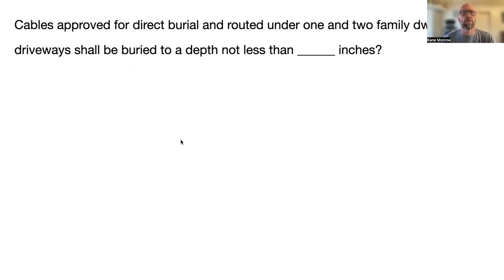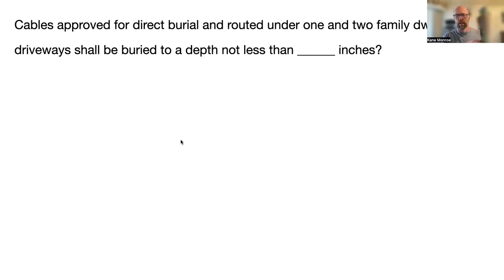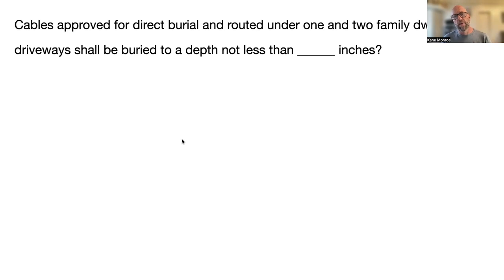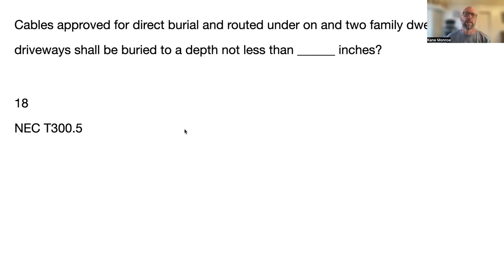Next question: cables approved for direct burial and routed under one- or two-family dwelling driveways shall be buried to a depth not less than blank inches. If you have a tabbed codebook, one of those tabs covers burial depths. Look up 'burial depths' in the keyword index — it'll take you to Table 300.5. The answer is 18 inches.